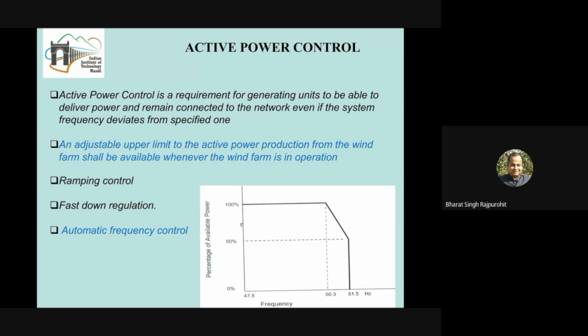And finally, there is automatic frequency control. What is the meaning of automatic frequency control? As the frequency varies within a band in Indian conditions, the power generation should also be able to change so that power is always supplied in such a way that it supports the frequency being maintained at the nominal frequency of 50 Hertz. In one sense, this is possible for a wind turbine, because we can reduce the output from a wind energy conversion system by controlling the power electronic system or the blade pitching mechanism.